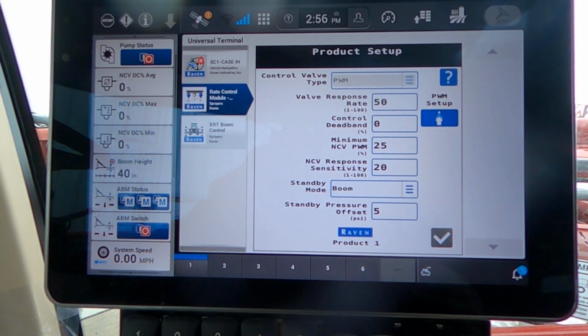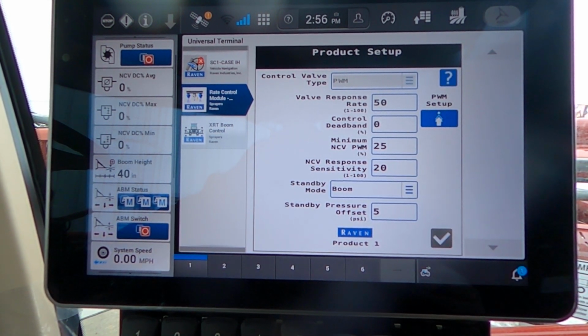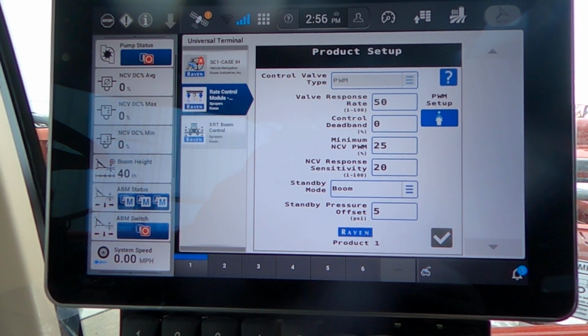Minimum NCV PWM. Your NCVs will only go down to 25% duty cycle. So once you drop down to 25%, it will actually over apply if you go too slow. So you'd have to speed up. So they recommend a minimum NCV duty cycle of 25. We don't recommend going lower than that.